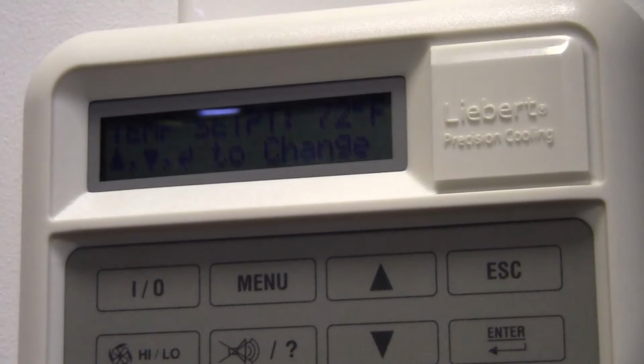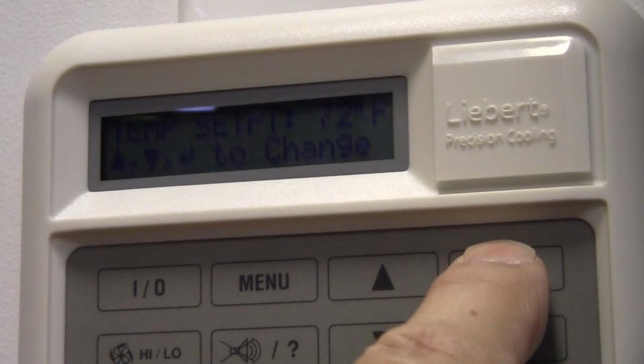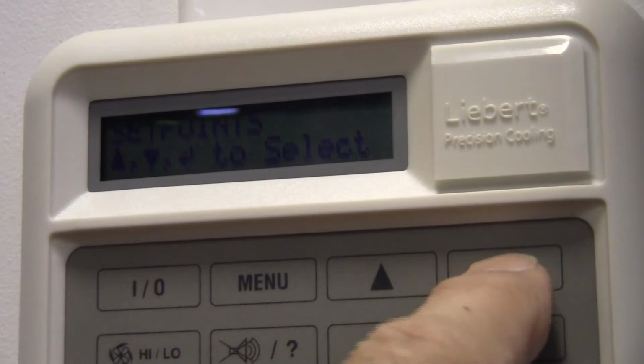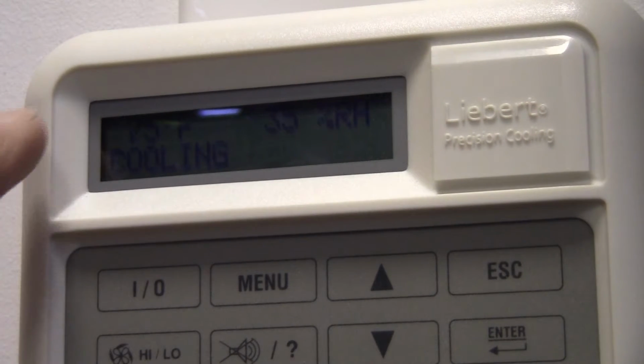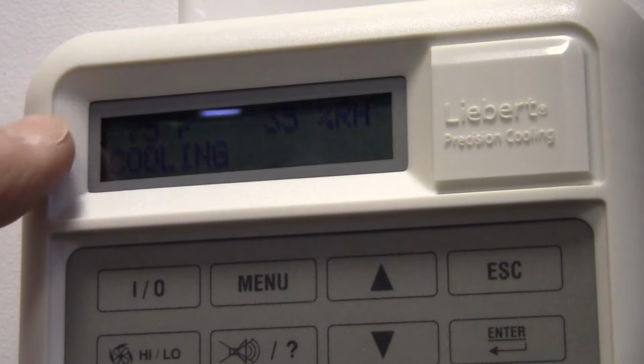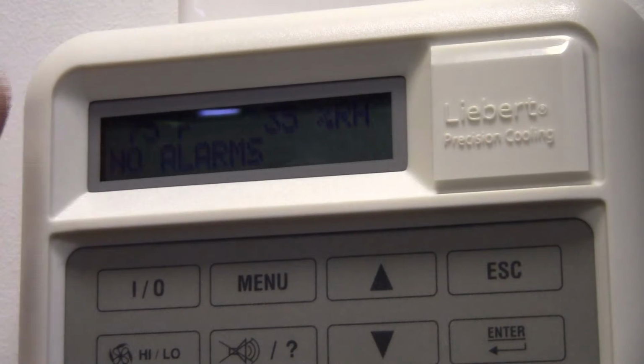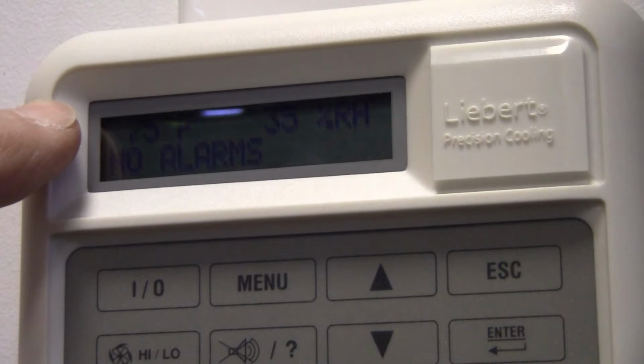Okay, now I want to just cycle the compressor off according to the thermostat. Now we know that the set point is set at 72. Hit the escape button a couple of times, and that's going to give you your room temperature, which is 75 degrees. So I'm going to take my set point, I'm going to set it to 76 degrees, shutting the compressor off.